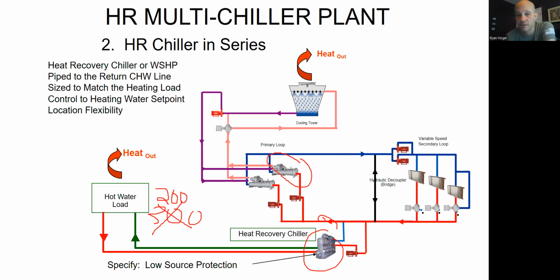It's already on, right? So these chillers can still be variable capacity chillers over here, and heat recovery, and they can ramp down if your load goes lower. But it doesn't really make a lot of cost-effective sense when you do that. I don't want to put in a 1,000-ton chiller that's going to almost always be ramped down to 300 tons and hardly ever need more than that, right? So I don't want to size it for my cooling load. It's much cleaner to size it for the heating load.